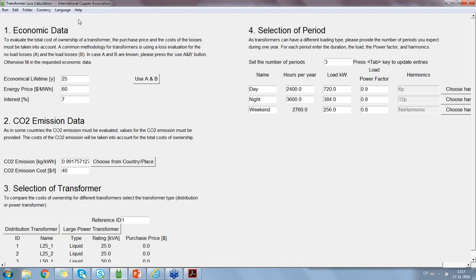The next step is that we would like to know what electricity price you are using, and also your interest rate. I think 7% is nowadays perhaps a little bit high on our side, but still, let's assume this is correct, then we can use those data. Another way which you very often see is that manufacturers ask for a load loss evaluation value and a no load loss evaluation value. Very often you have to fill in what is called an A and a B factor, where A is an evaluation for your no load losses, and B is an evaluation of the load losses.